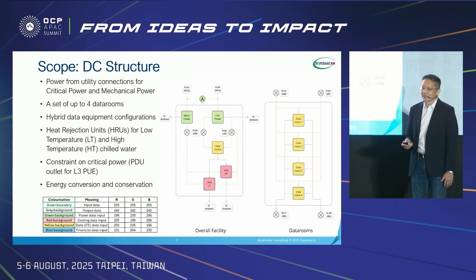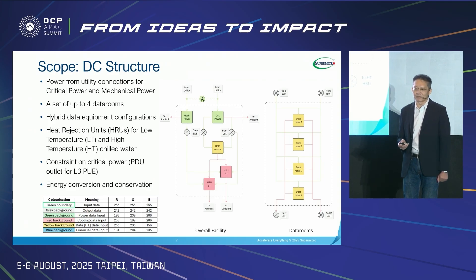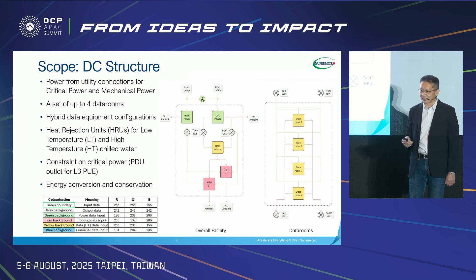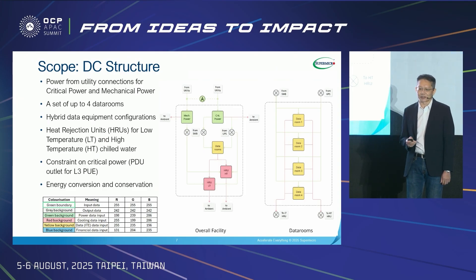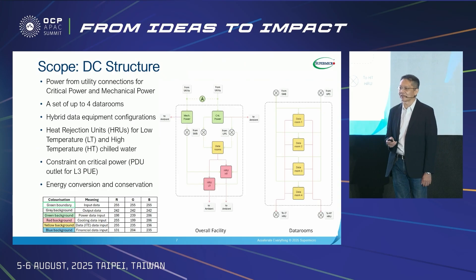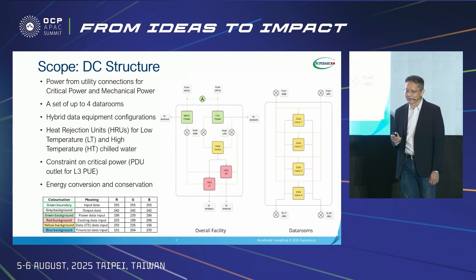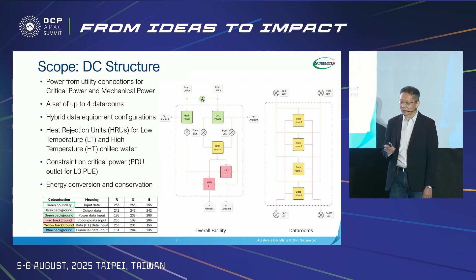Essentially, the model solves a set of energy conservation equations for the facility, accounting for the performance and efficiency of each process and sub-process contained within. There are 66 equations being solved simultaneously. This is the reference architecture, with power — shown as green arrows — from utility connections for critical power and mechanical power, a set of up to four data rooms, including red arrows for heat flows via two pathways, and heat rejection units (HRU) for low-temperature and high-temperature chilled water.